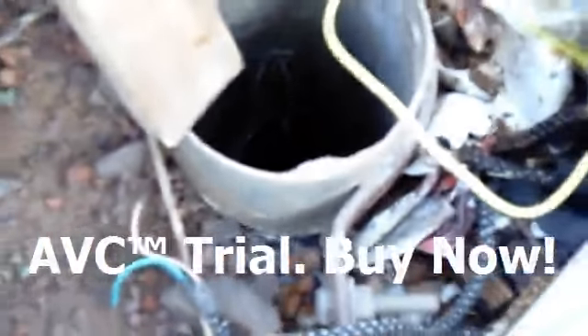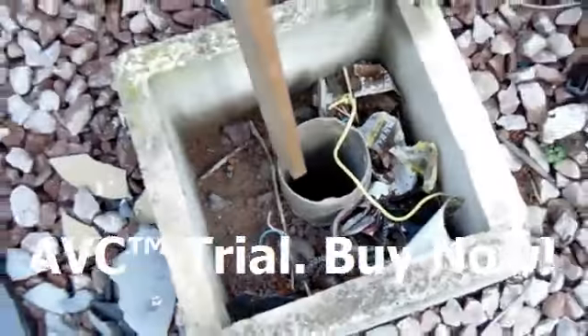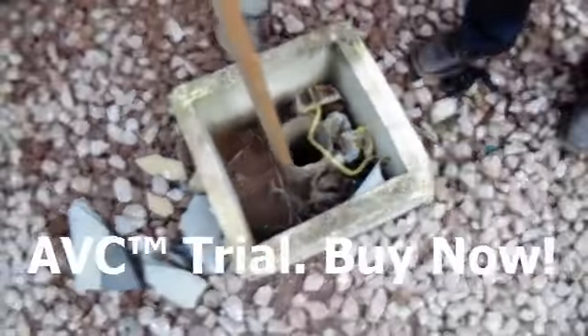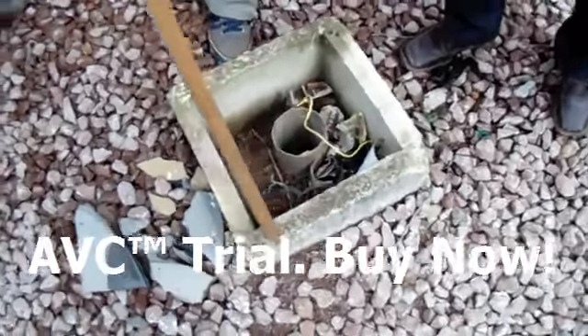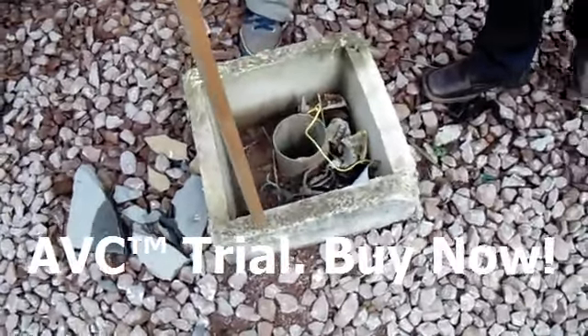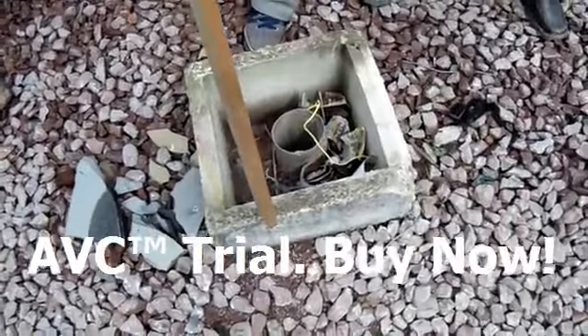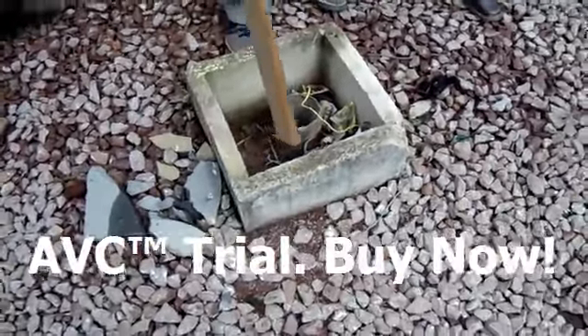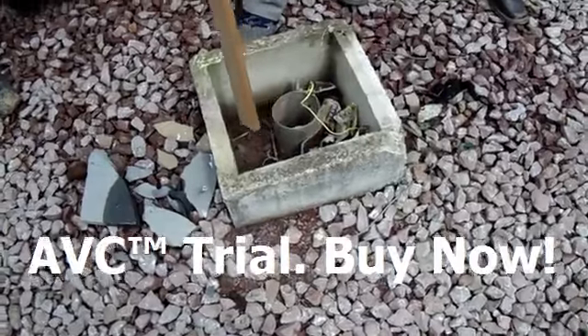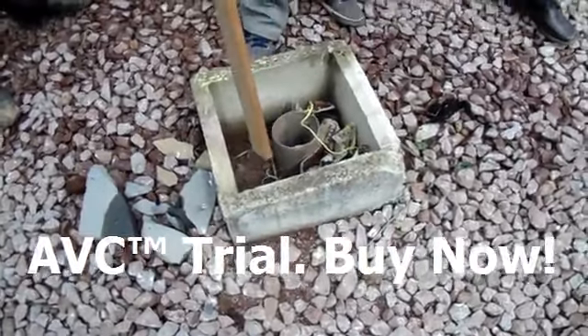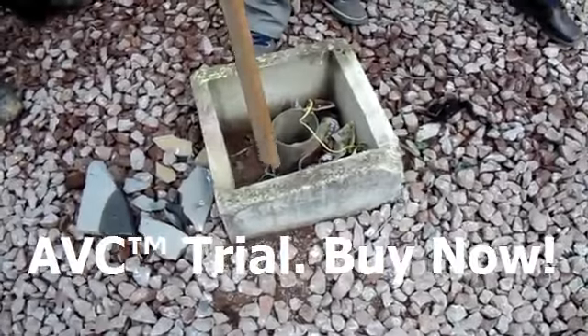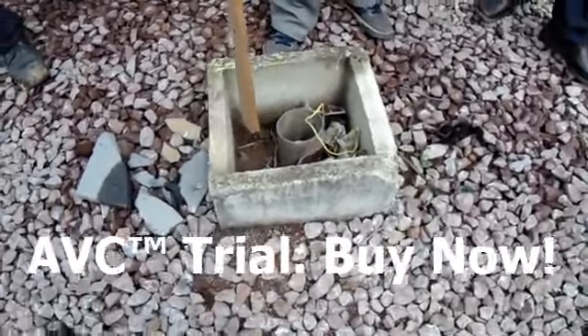Why is this pipe given? Because during the summer season you have to pour water to keep this pit moist, because for the substation earthing, the earth resistance should not be more than 1 ohm. So the first time you make it, along with this copper plate, you pour charcoal and salt to decrease the soil resistivity.